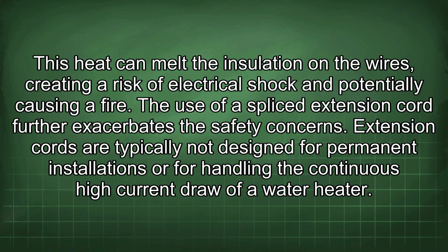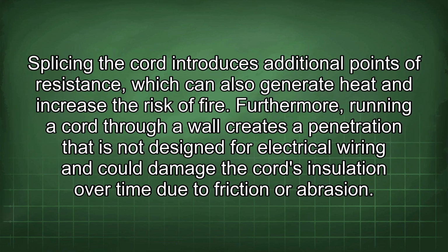The use of a spliced extension cord further exacerbates the safety concerns. Extension cords are typically not designed for permanent installations or for handling the continuous high current draw of a water heater. Splicing the cord introduces additional points of resistance, which can also generate heat and increase the risk of fire. Furthermore, running a cord through a wall creates a penetration that is not designed for electrical wiring and could damage the cord's insulation over time due to friction or abrasion.